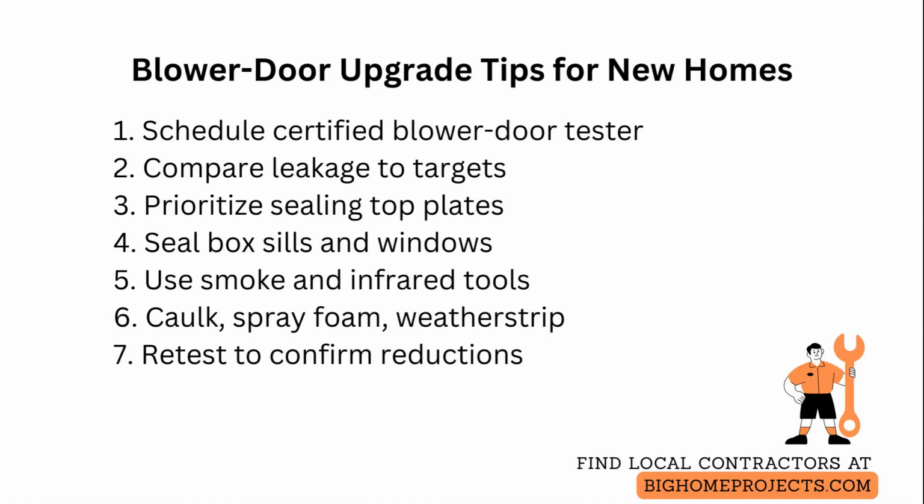During the test, the technician will depressurize the house to reveal whole house leakage and produce a leakage rate such as air changes per hour at 50 pascals, which lets you compare performance to code or best practice targets.